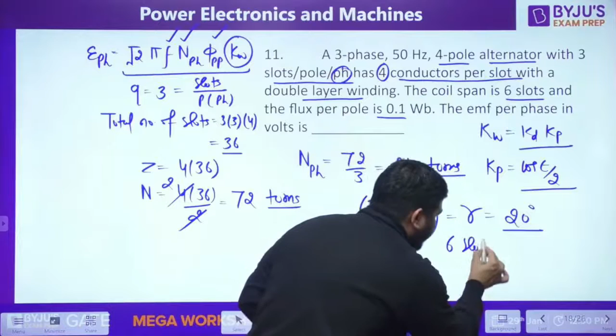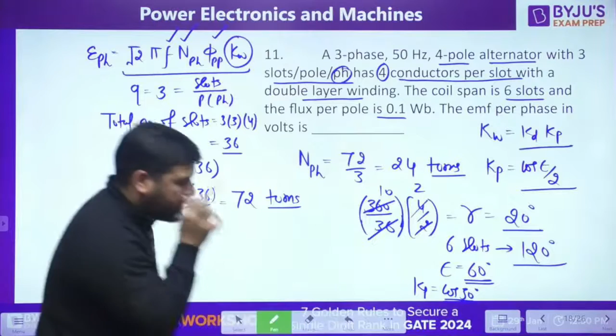Now, coil span is 6 slots, which means 120 degrees electrical. It means the coil is short pitched, short pitched by 60 degrees. So the chording angle is 60 degrees. If you know the chording angle, you can easily calculate Kp. So Kp came out to be cos 30 degrees.